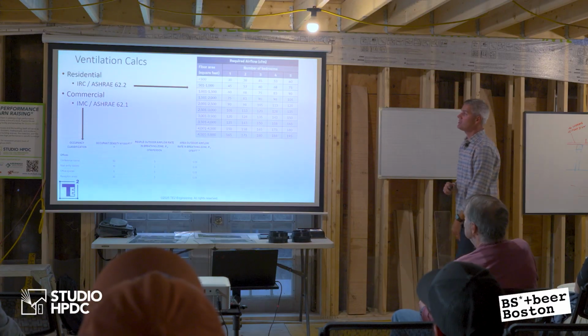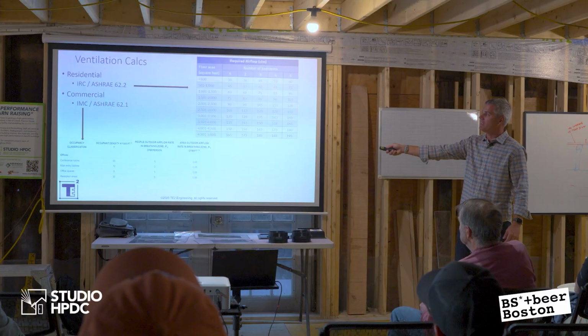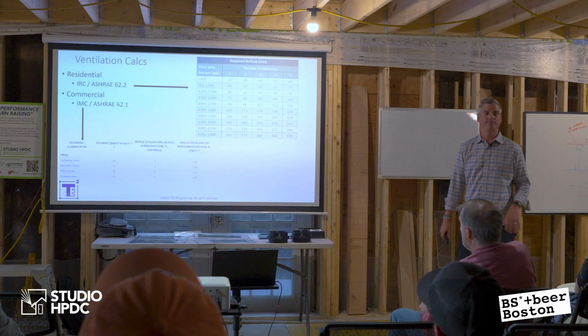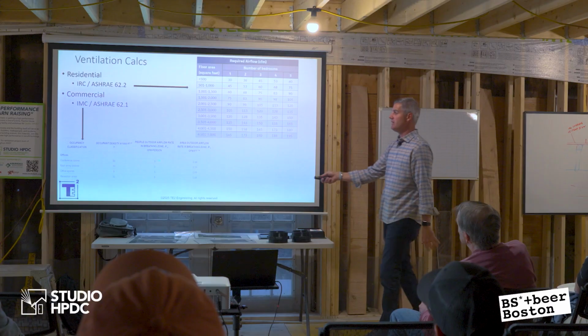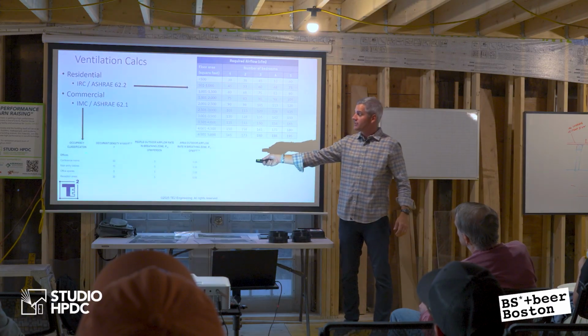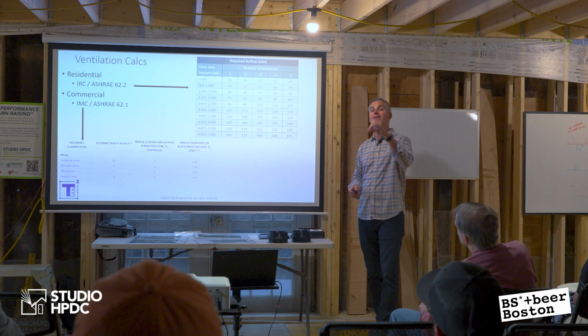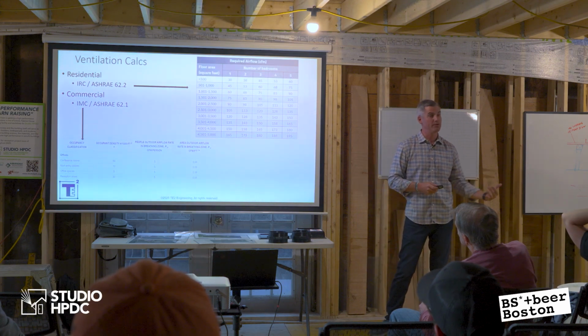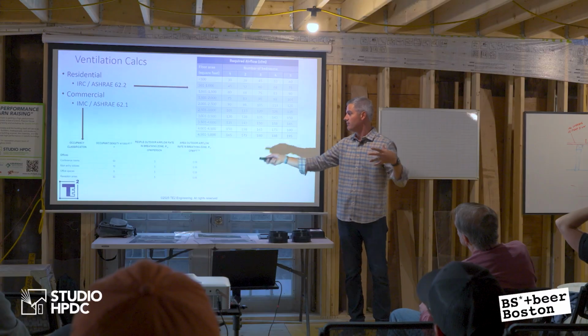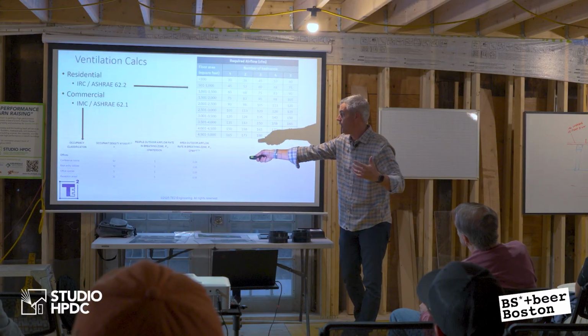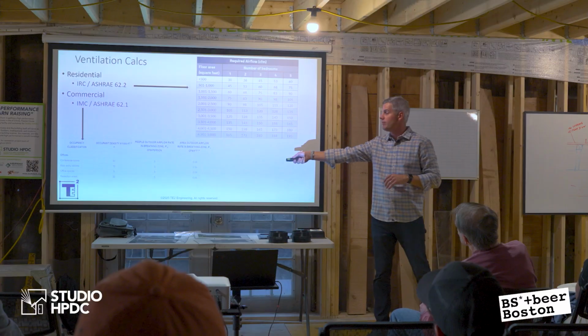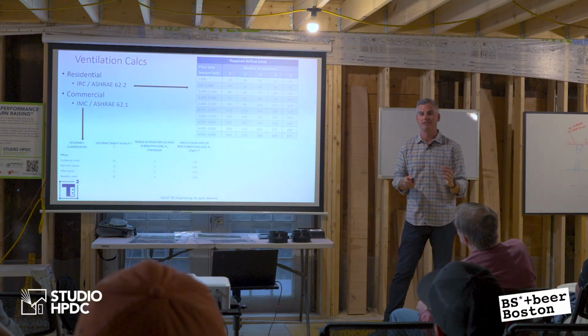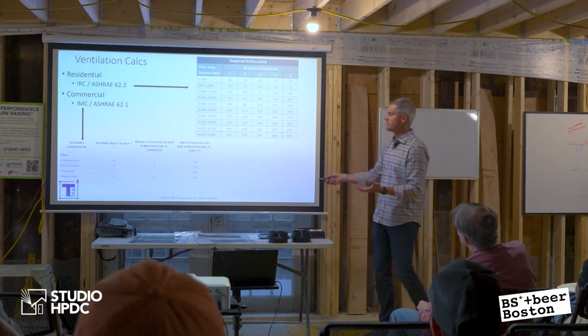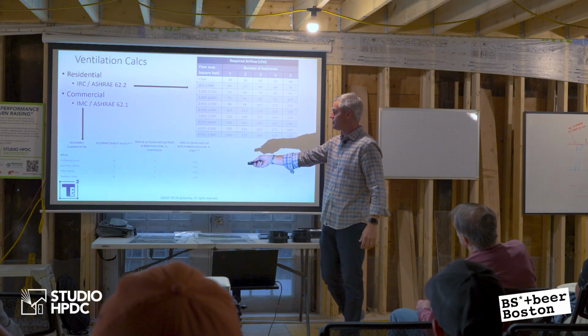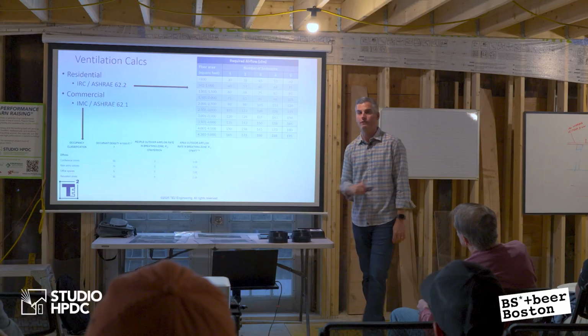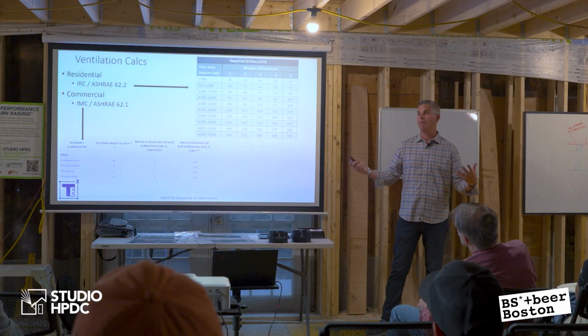The next one is ventilation calcs, right? So for residential, they make it really easy. What's your square footage and how many bedrooms do you have? Really, really simple residentially. Commercially, like a building like this, we call this commercial, it's a lot more challenging because you have to pick your occupancy classification per zone or per area of the building. So we might define this as a conference room, or we might call upstairs an office space, right? Maybe a reception area. We're going to define these spaces based on how it's going to be used. And that's going to tell us what the occupant density is, how much air do we need per person, and how much air do we need per square foot. That's outdoor airflow rates. We can do that math out. Okay.